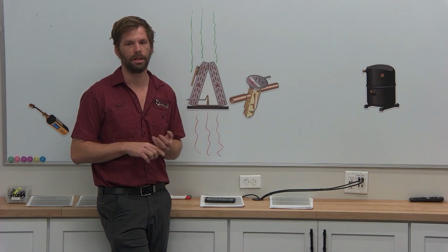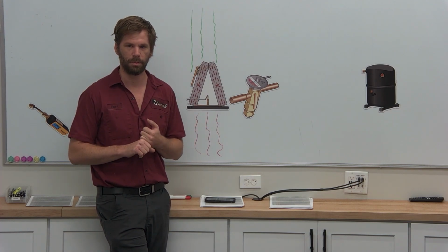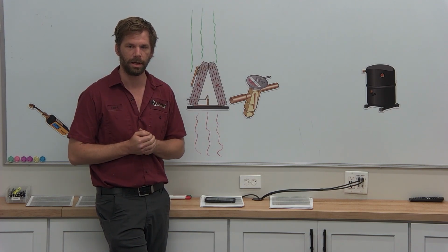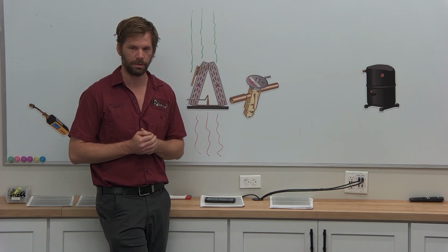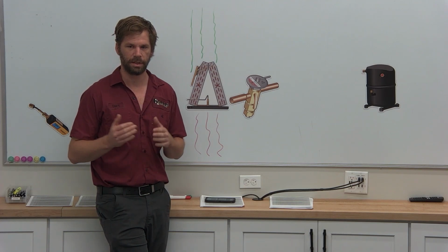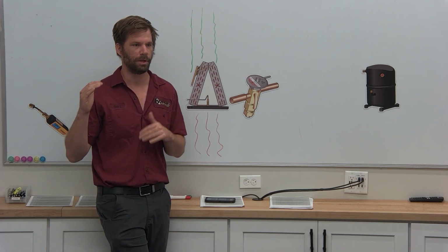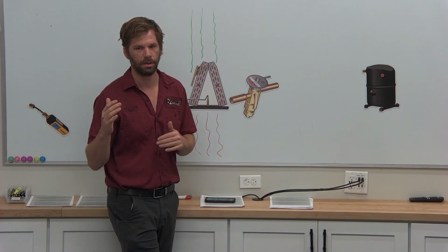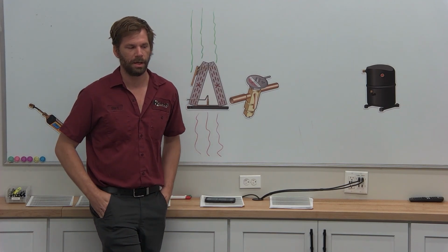Perfect scenario would be a lot of short cycling, it only runs for a couple minutes, hits temperature, shuts off. We can dramatically lower that blower speed. We can put it in constant dehumidification. If it's still hitting their set point, but now really focusing on dehumidification, that's great.